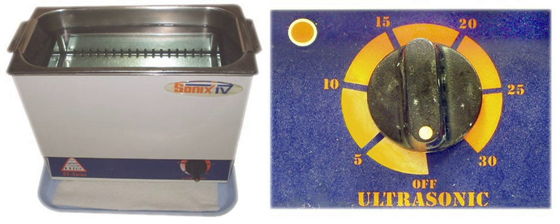Ultrasonic cleaning is a process that uses ultrasound, usually from 20 to 40 kHz, to agitate a fluid. The ultrasound can be used with just water, but use of a solvent appropriate for the item to be cleaned and the type of soiling present enhances the effect.